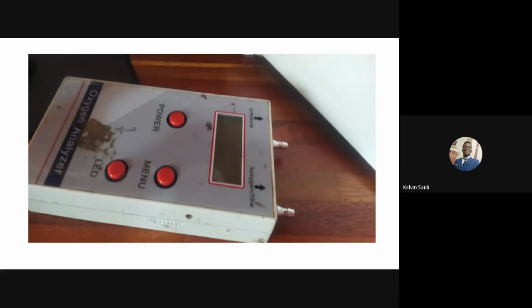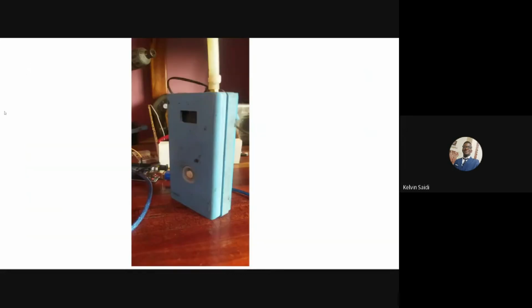As you can see from the graphics, we have the two types of oxygen analyzers that we have at our Open O2 training center. Oxygen analyzers are very important tools, and they are used for troubleshooting oxygen concentrators. I recommend any workshop that works on oxygen concentrators to have this device. And if you cannot afford to purchase one, you can build one of your own. If this is the approach you are going to take, an obvious factor you have to consider is the type of oxygen sensor you have to use.